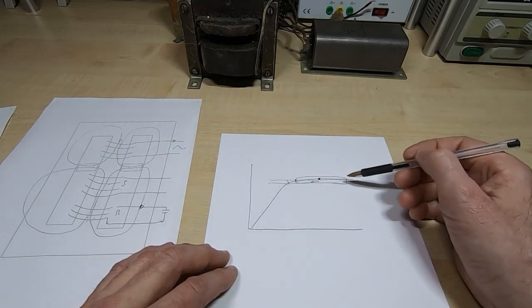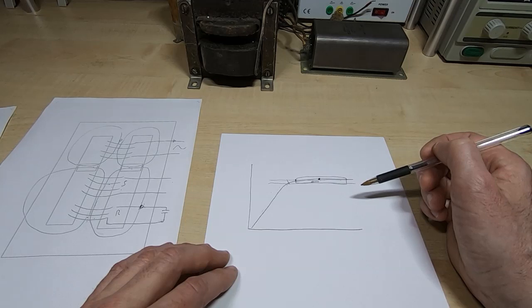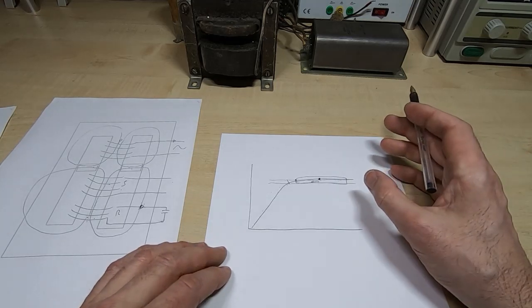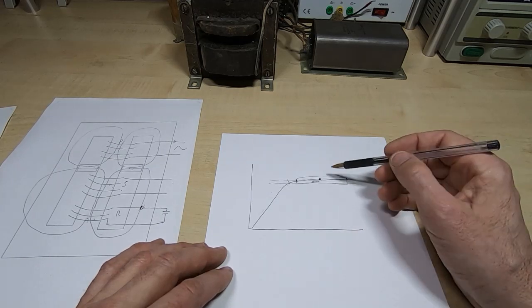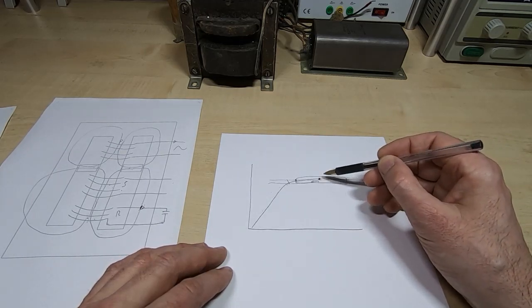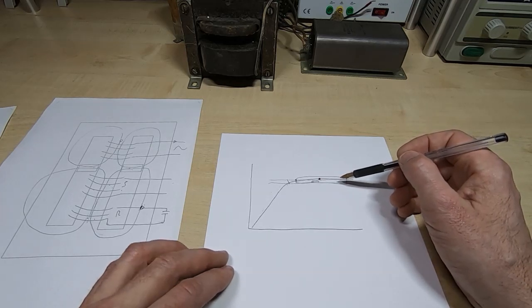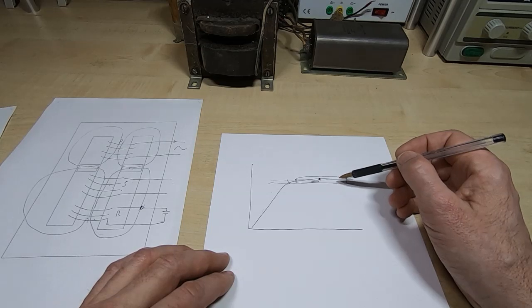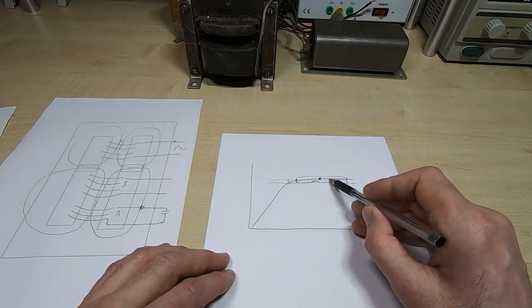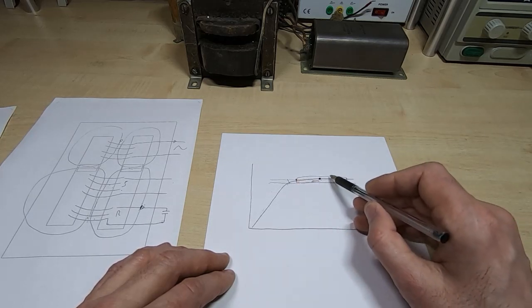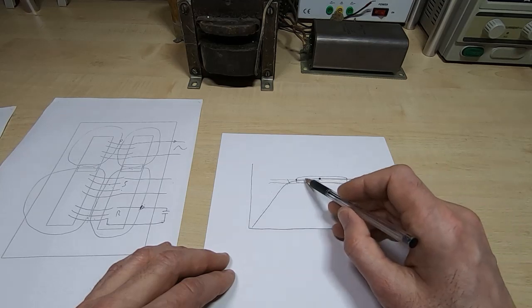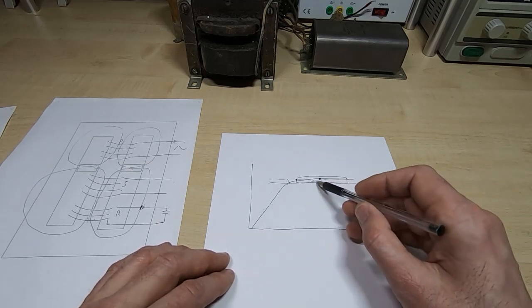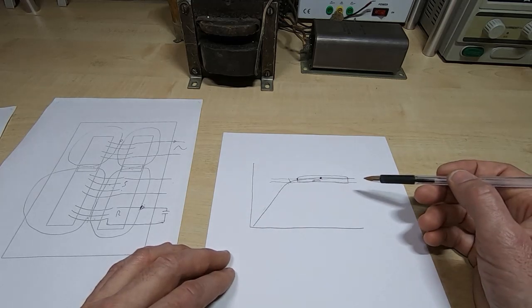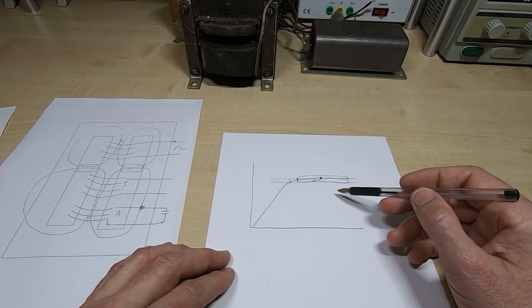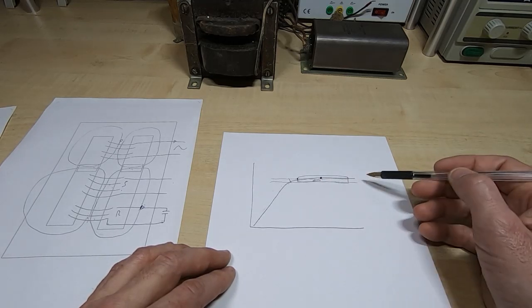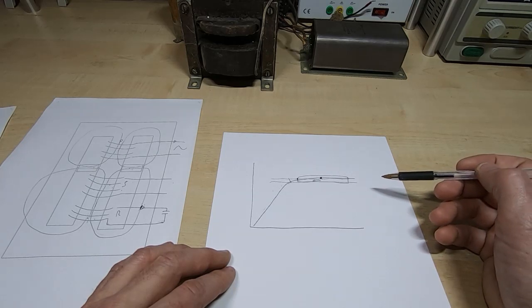So whichever way it moves, the change in voltage is going to be very small. This is the principle on which it operates: because the secondary is in a flat portion of the saturation curve, the transformer is effectively operating in a range where changes in load or changes in input voltage don't really affect the output to any large degree. As long as the transformer is properly designed, we can have a 10-to-1 isolation ratio, where the change in output voltage can be only 10% or less of the change in input voltage.